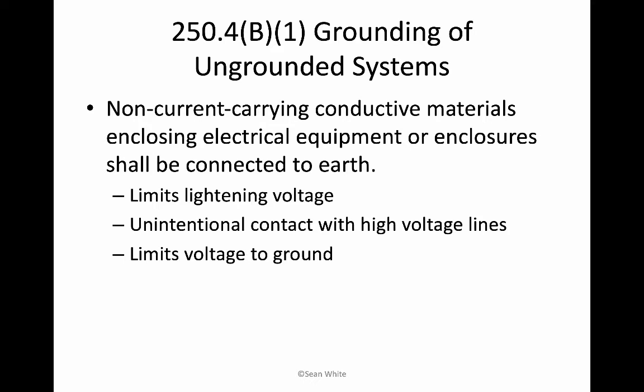We also ground, of course, our grounded system. Equipment grounding is important. We want to bond all these things together: equipment enclosures, anything that's metal that could carry current. Non-current carrying conductive materials, as it says in 250.4(B)(1), non-current carrying conductive materials enclosing electrical equipment or enclosures shall be connected to earth.